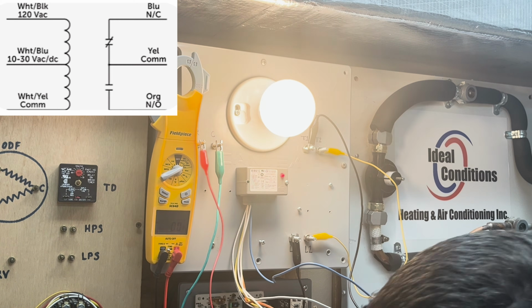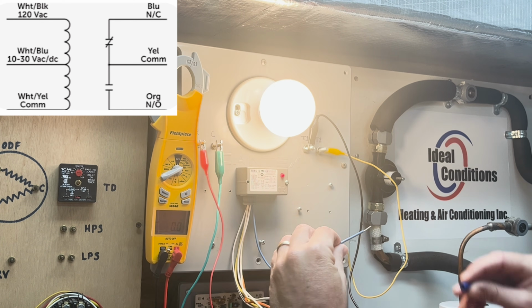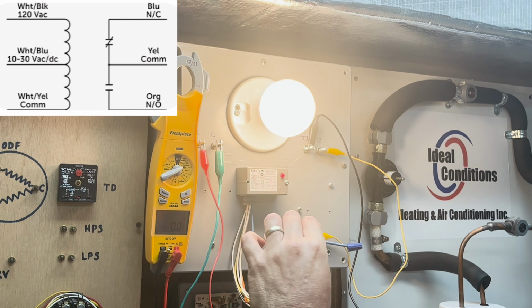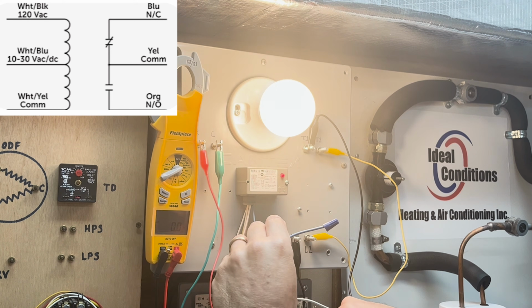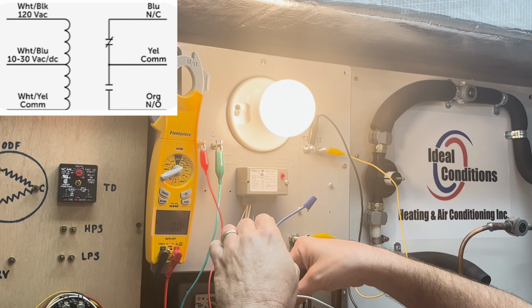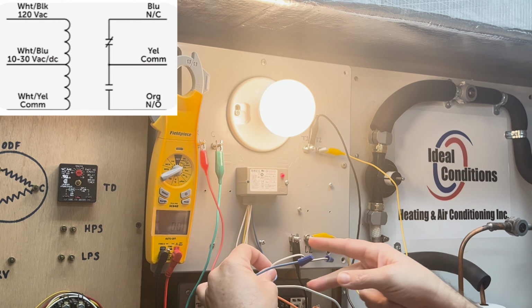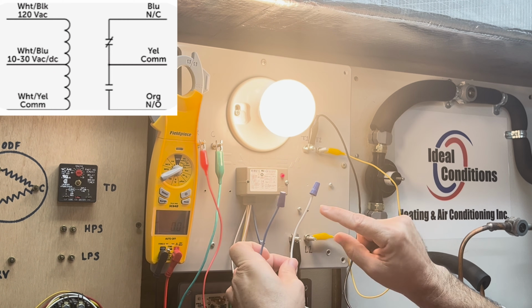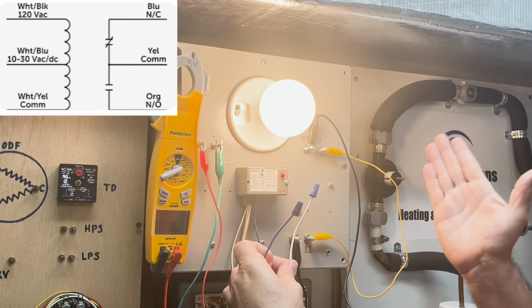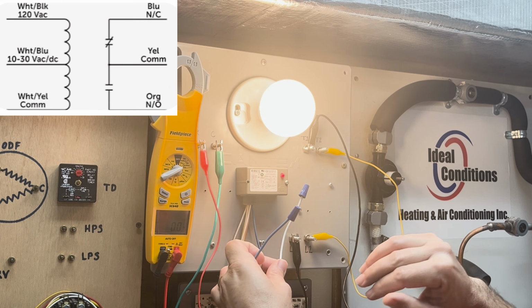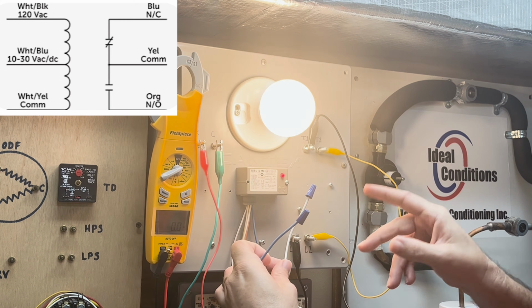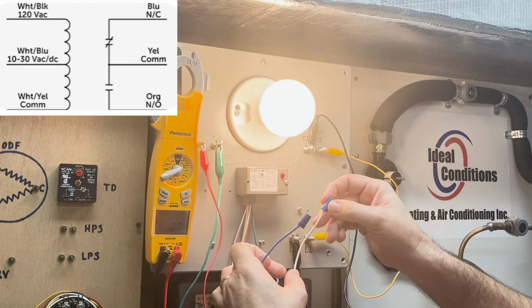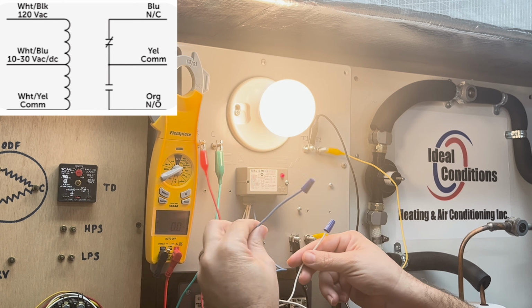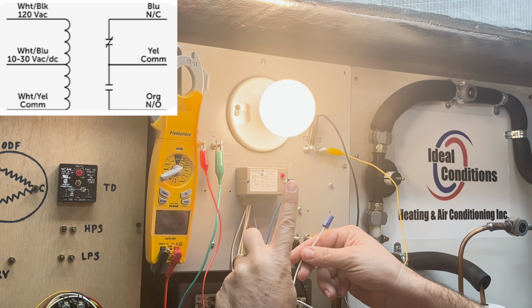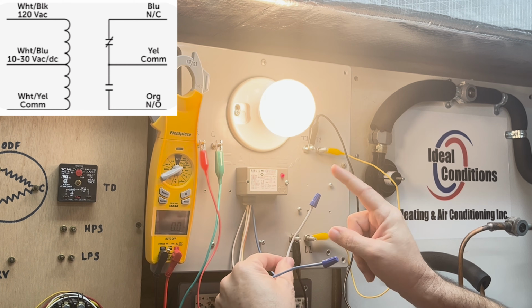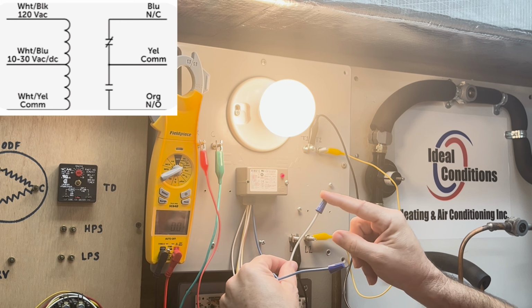Now, as you can see here, I have a spare wire. I'm going to go ahead and cap that off. My other spare wire, which was white/black, I'll go ahead and show you that. I actually had a wire nut on that one the entire time. White/black would be used if I had 120 volts and I wanted to put it on this and I was using my common as a neutral, so I had a path for coil voltage. So this is my one spare contact that I'm not using, my normally closed contact, so I'm capping that off. And then I'm going to cap off my 120 side for my coil that I'm not using.